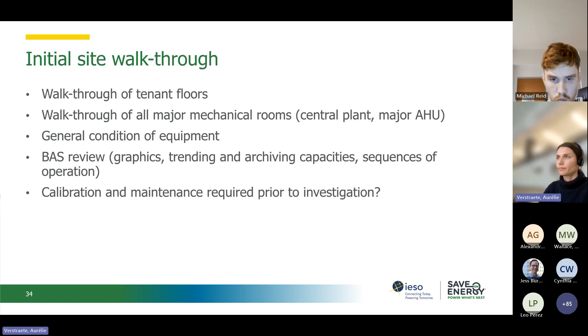Then a walkthrough of all major mechanical rooms, for example the central plant and major air handling units. The commissioning provider will also have to address the general condition of equipment, and spend a lot of time on a building automation system review: graphics, trending capacity, sequences of operation. And then maybe detect if calibration and maintenance is required prior to investigation.